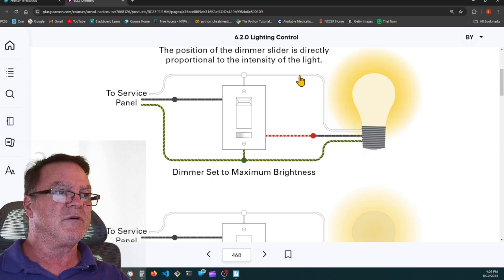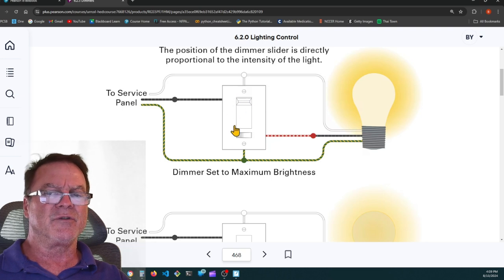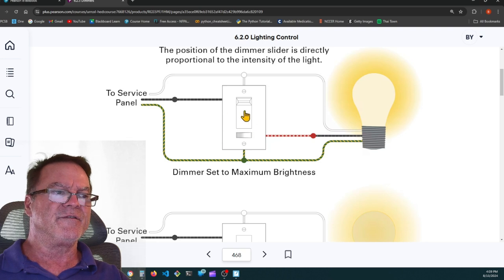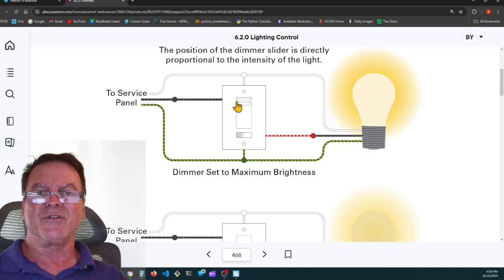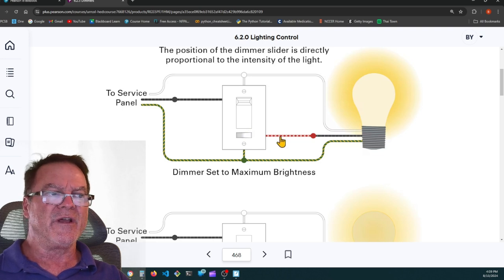Here they have the neutral coming, and they've actually taken the neutral to this. I'm wondering if this is an electronic dimmer. If it uses a neutral, it's probably an electronic dimmer. And then the hot goes to the dimmer and feeds it. Then they have the red switch leg coming to the light. So the hot is feeding the electronic dimmer, and the neutral is allowing the dimmer to use a small portion of that electricity to power it, and then the output is on the red switch leg, and it can vary the output of that switch leg.